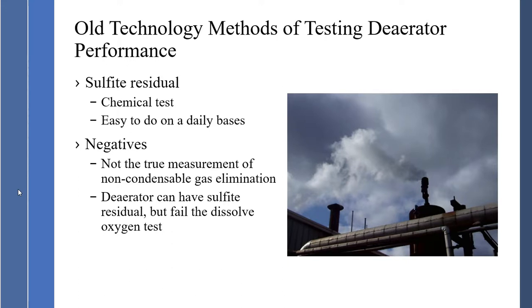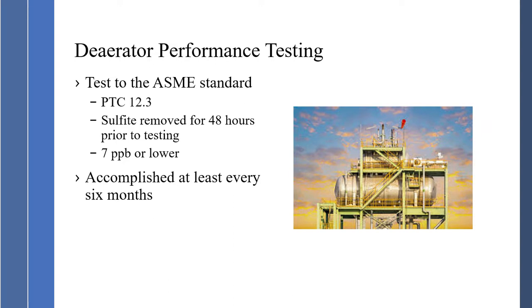Another method is sulfite residual — chemical tests that are easy to do on a daily basis and should be done on a daily basis. The negative is that it is not a true measurement of non-condensable gas elimination; it just tells me I have sulfite residual. A deaerator can have sulfite residual but fail the dissolved oxygen test. I have seen deaerators that have sulfite residual and when we do the ASME test, they test out at 300 parts per billion. Therefore, we must do the ASME test, which is ASME standard PTC 12.3. You have to remove the sulfite for 48 hours prior to testing because we want to measure true deaerator performance, which is 7 parts per billion or lower. This should be accomplished every 6 months — some plants do it monthly, but at least do it every 6 months.